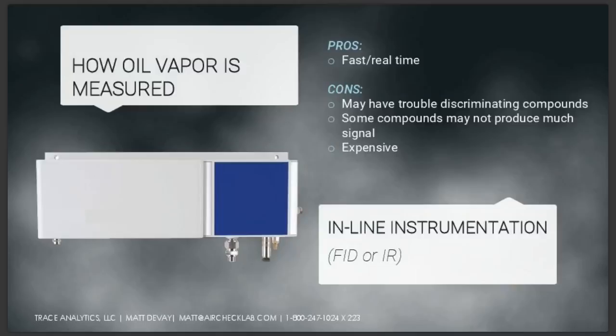Other things about them, they're really expensive. They do also require outside calibrations. So with these, since it's a permanent install, you've got to now pay someone to come on site to maintain and calibrate your really expensive device. And they don't really give universal results. So depending on what your individual components of your oil vapor may be, some of them are going to give better responses and indicate a presence of more vapor than other compounds. So your more common mineral oil type constituents may give you very high responses. Your more common silicone type oils are going to give you lower responses. So the accuracy is kind of dependent on interpretation in that case. And they are hugely expensive. Expect to spend a lot of money if you're going to install these at all your points of use.